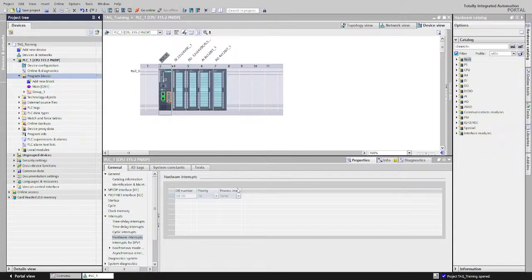What can cause a programming error? For instance, you can have an overflow. You have a counter linked to the number that the memory can count. If they are counting more than I think 32,76-something, or about to go negative, you can cause an overflow in the system. Or you are multiplying and the number is too big for the memory to contain, it gives you a programming error.